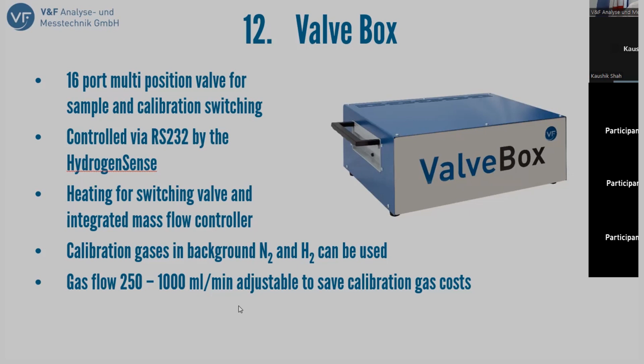Inside, there is also a mass flow controller. This is mainly for an application when you have gas cylinders which don't have a lot of volume or a lot of pressure. Then we can regulate the amount of gas that is used by the instrument in order to have sufficient gas to do a complete analysis.